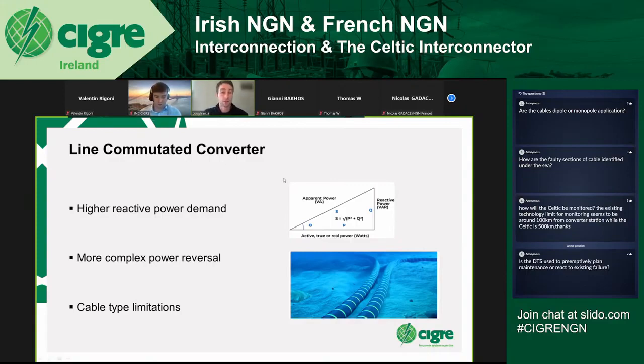A few reasons why we didn't go down that path: firstly, LCCs have a higher reactive power demand, meaning they consume reactive power where they're connected. They also use thyristors, which are controlled at a point on the waveform. Because of these two reasons, they have to be connected to a strong part of the network, which reduces your flexibility in selecting the connecting point.